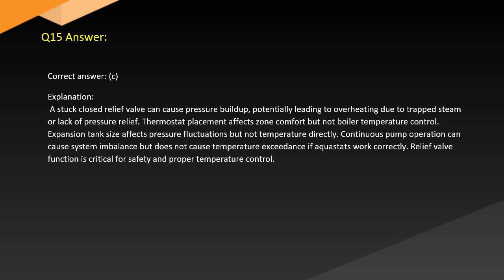Answer. Correct answer, C. Explanation. A stuck closed relief valve can cause pressure buildup, potentially leading to overheating due to trapped steam or lack of pressure relief. Thermostat placement affects zone comfort but not boiler temperature control. Expansion tank size affects pressure fluctuations but not temperature directly. Continuous pump operation can cause system imbalance but does not cause temperature exceedance if aquastats work correctly. Relief function is critical for safety and proper temperature control.